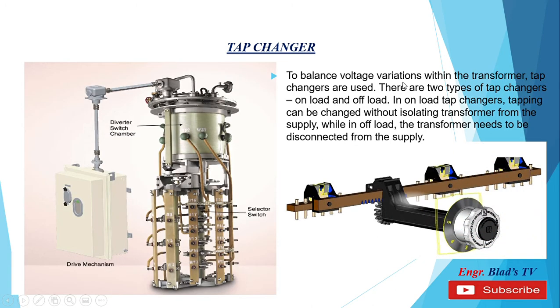Tap changer. To balance voltage variations within the transformer, tap changers are used. There are two types of tap changers: on-load and off-load. In on-load tap changers, tapping can be changed without isolating the transformer from the supply. While in off-load, the transformer needs to be disconnected from the supply. In this picture we can see a sample of an on-load tap changer, while in this picture we can see a sample of a de-energized or off-load tap changer.